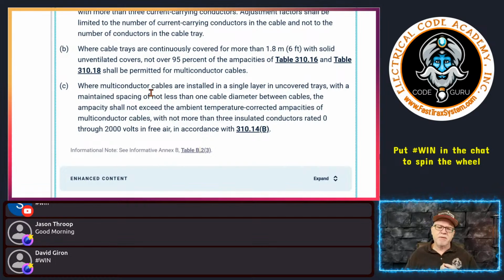This is saying, look, if you take those multi-conductor cables, okay, and you install them in a single layer, and you maintain spacing of not less than 1 cable diameter of the cables you're using between these cables, okay, so you're maintaining spacing, right? Got a cable, you have a gap that's the width of the cable, you have another cable, and you have a gap, and of course, you remember, we're sizing our cable tray to accommodate that, so we're adding the width of the diameter of the cable, plus the diameter of a space, which represents another cable, and then to have another cable, so you're taking all that into consideration to find your minimum tray width, right, on the interior.